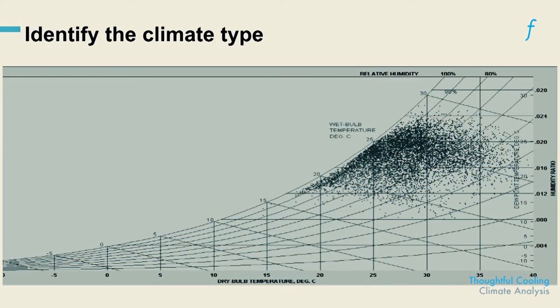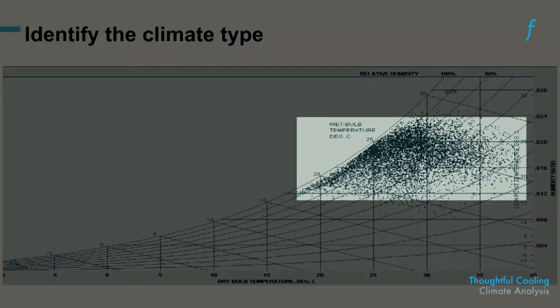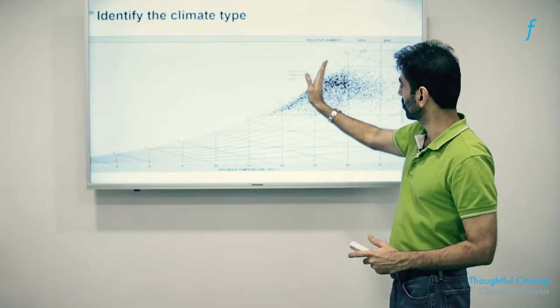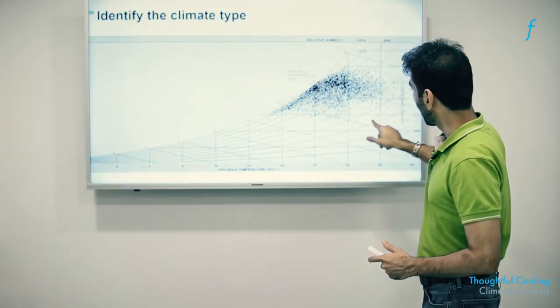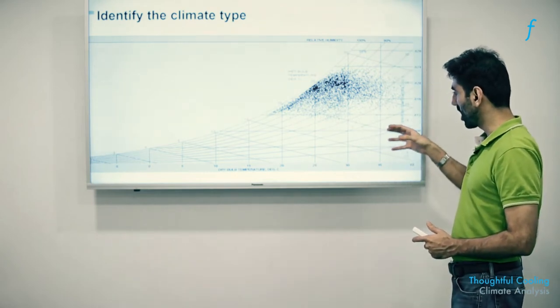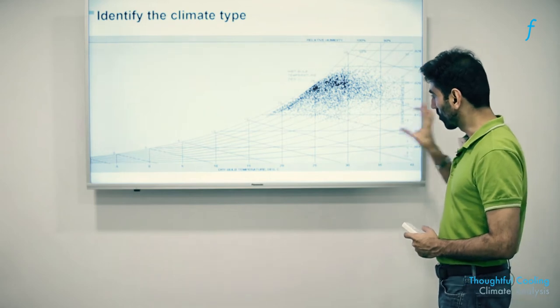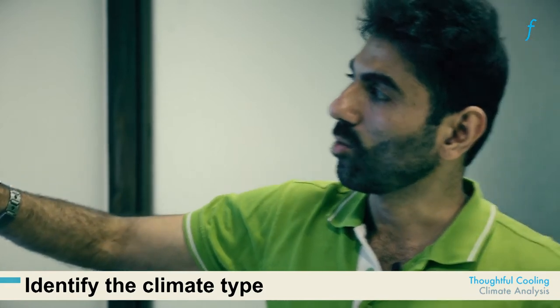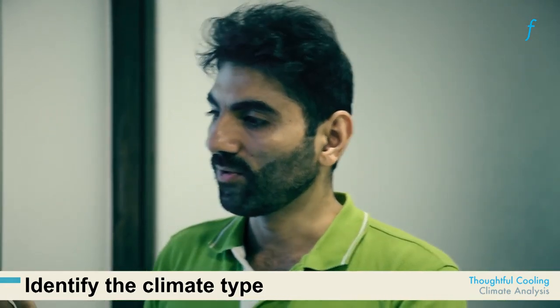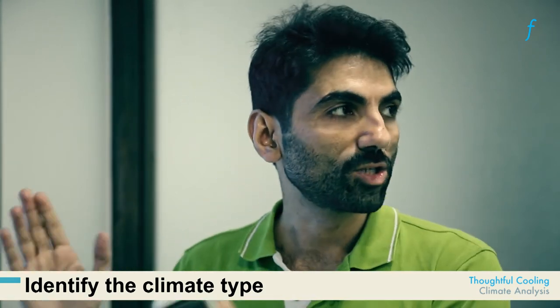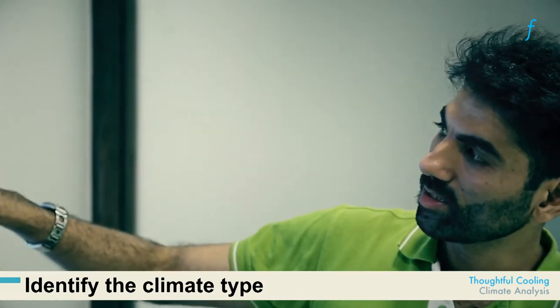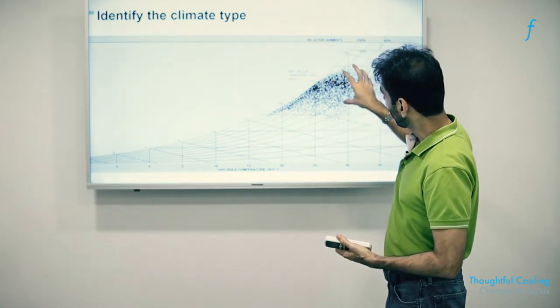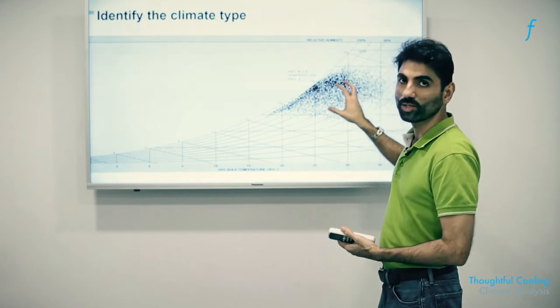So this is a chart which indicates a lot of clustering around the high humidity region which is close to the saturation line as you can see. Very few hours are present in this area which is the dry and hot part of the psychrometric chart. So of course this is not a hot and dry place. This is most likely a humid place, and whether it is a hot and humid or a warm and humid, we will only be able to detect once we see the corresponding charts for other regions. But most likely this is the chart for a warm and wet region of India.